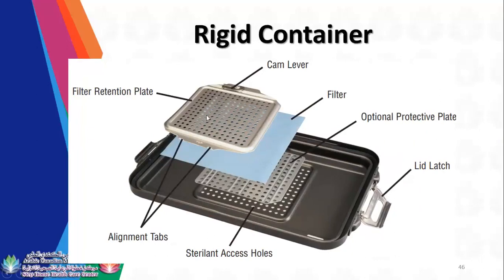So steam will enter here. It will be filtered by the tray liner or filter paper. Align the tabs; this should be aligned. The cam lever is your lock. For your retention plate, it should be intact and not bent. It should sit flat over the filter.